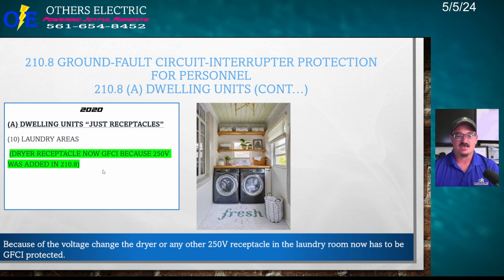Okay, here's a big one. 10, laundry areas. This didn't change. The only thing that changed is that before, laundry areas were required to be GFI protected, but only the 115 volt or 120 volt receptacles. Now, because the voltage changed, the dryer or any other 250 volt receptacle in the laundry room has to be GFI protected. So dryers now have to be on a GFCI breaker, 250 volt, or anything else, any 250 volt receptacle.